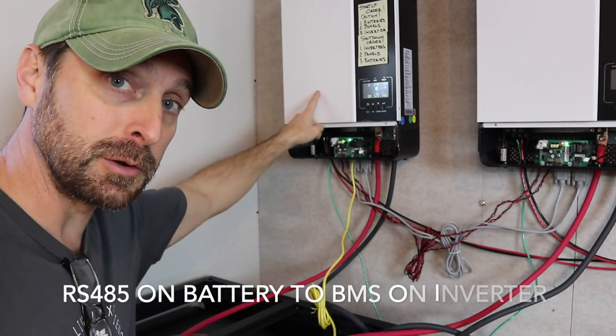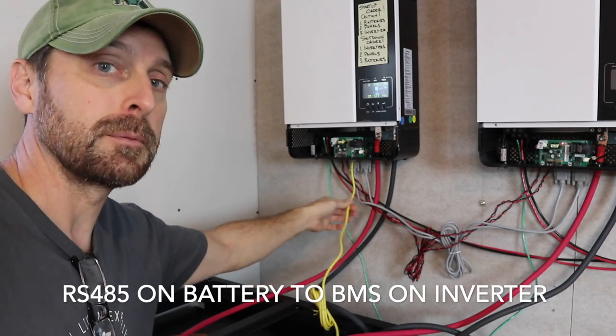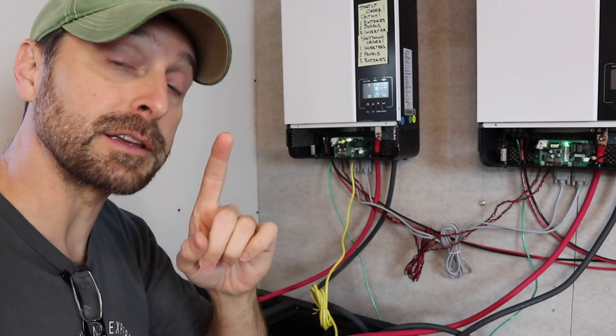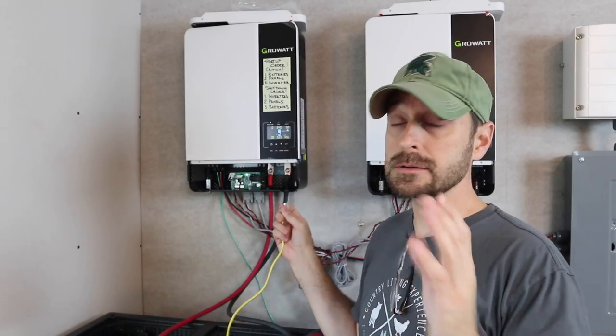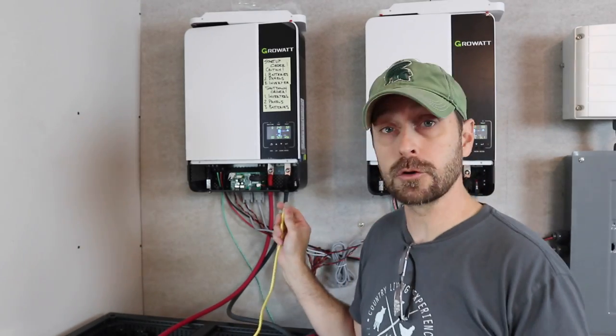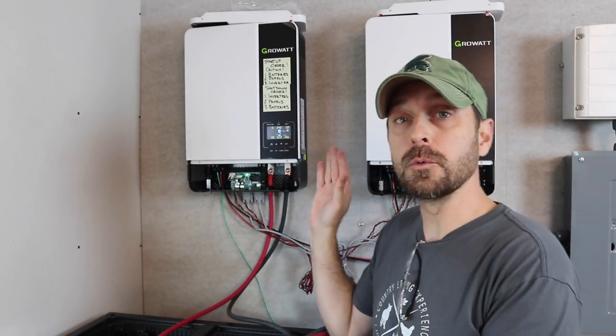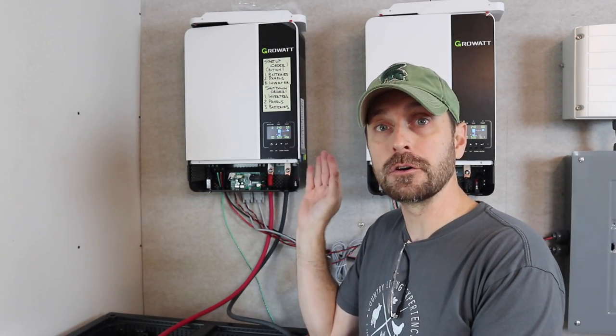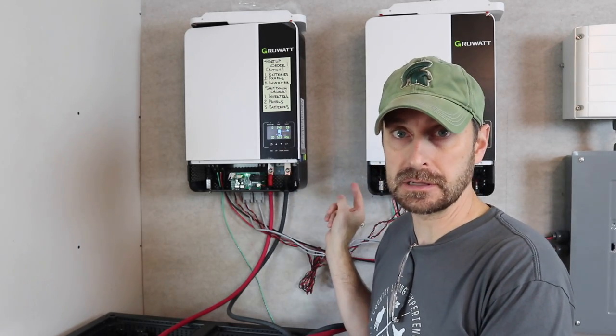So, brand new inverter, BMS port, plug it in there. Older inverter, RS-485 to RS-485. Now, something happened I'll have to get some clarification for you on: the order in which I turned on and off the inverters reset the master and the slave.